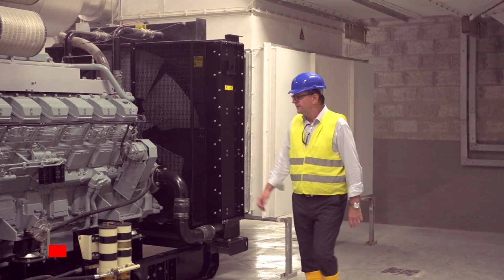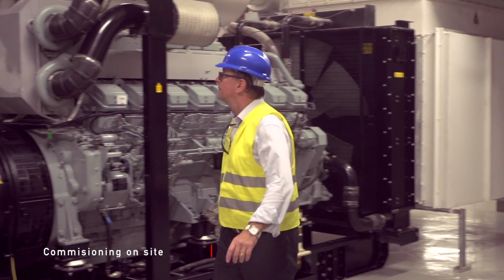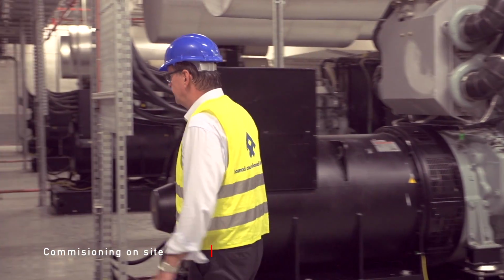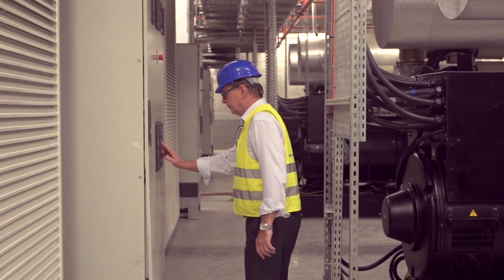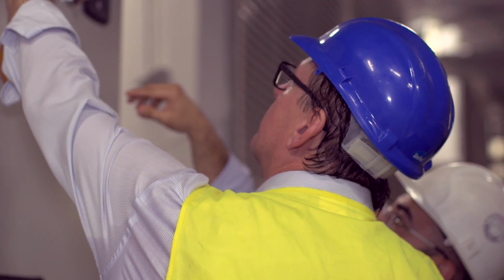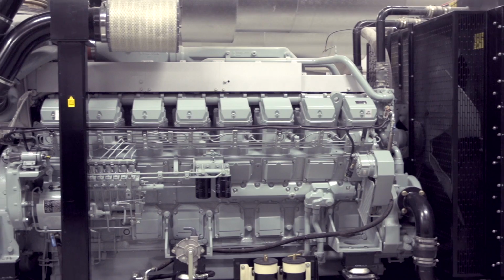We have studied the testing protocol together with the client. The units have been operated at their limits to ensure the rated performance in the heaviest circumstances. Synchronization times have been tested and measured. We also did 100% load step, sudden load decrease during operation, and very quick load variation, just to name a few.